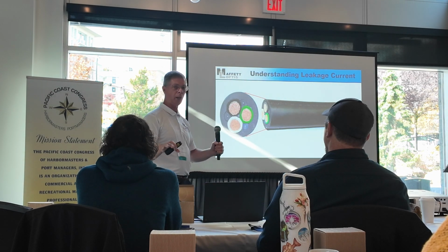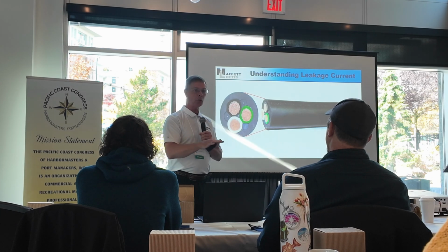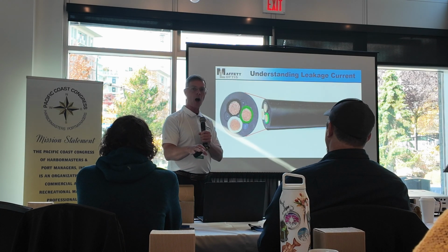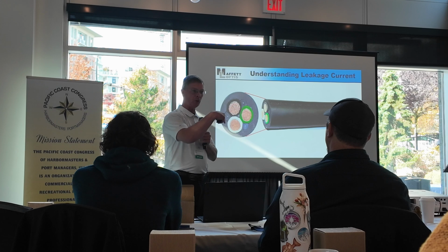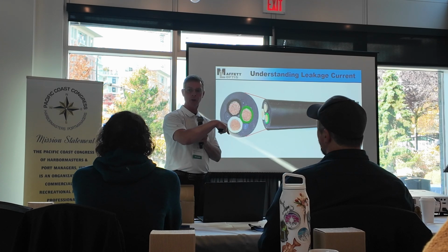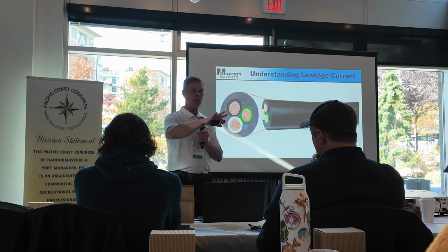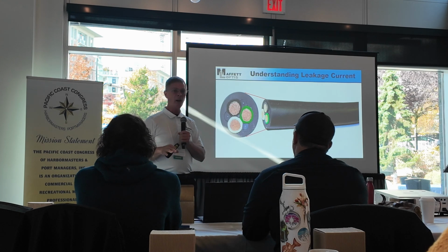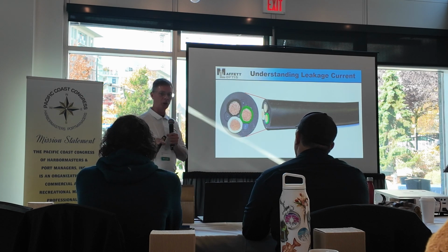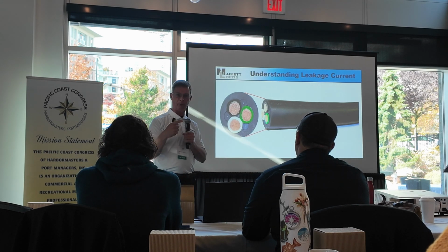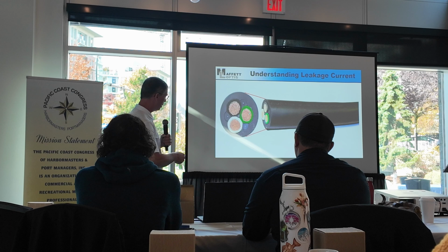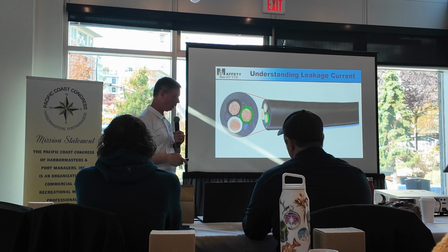Remember that equal potential plane: everything that you can touch is bonded to that green wire so that you don't get shocked. Okay? It goes back to the service, drives into the ground rod, attaches to the neutral of the service, and creates that equal potential plane, the equal voltage everywhere. Very, very important. If there is leakage current, generally it'll go back on that ground wire, or if there's fault current, it will go back on the ground wire, trip over current protection, kill the power and save your life. So that green wire is a very important piece of the cable.